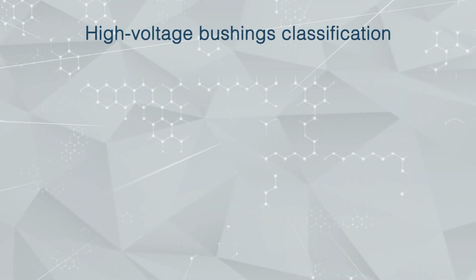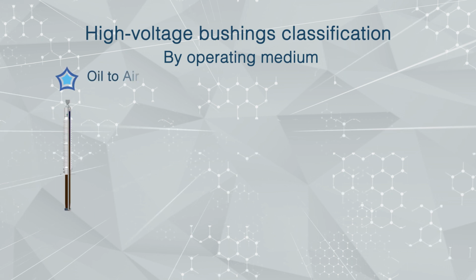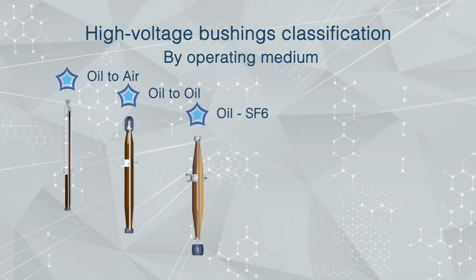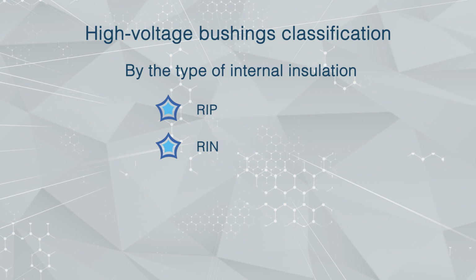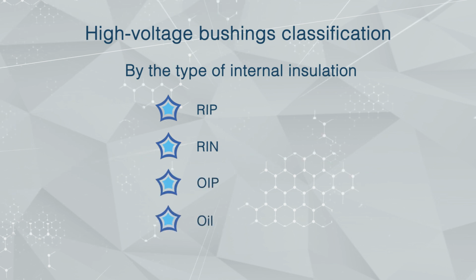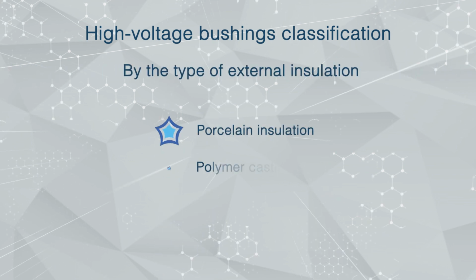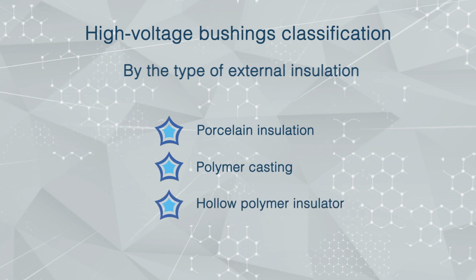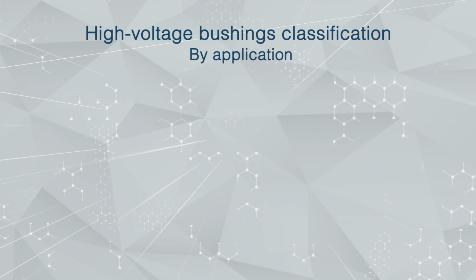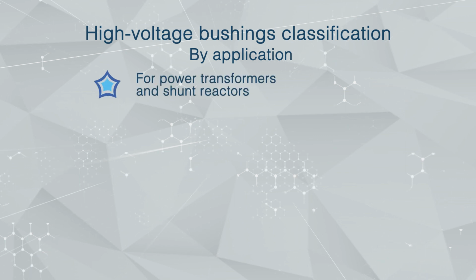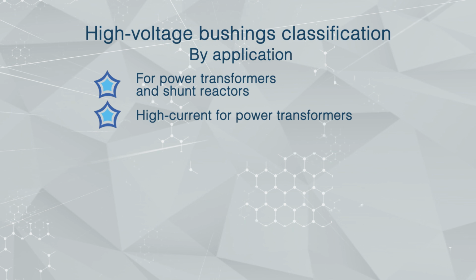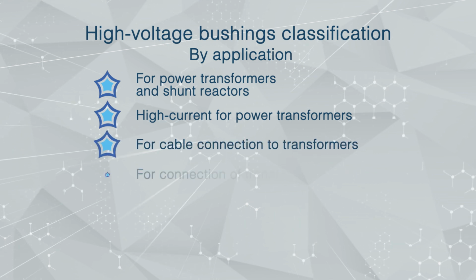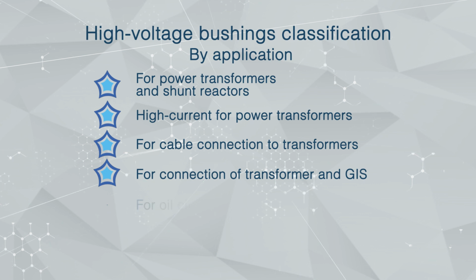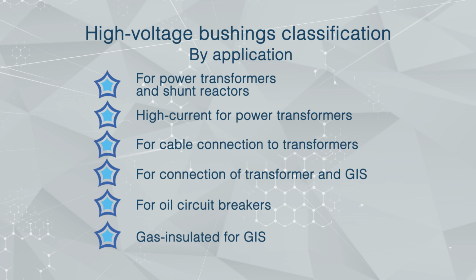High-voltage bushings classification. By operating medium: oil to air, oil to oil, oil to SF6, SF6 to air, air to air. By the type of internal insulation: RIP, RIN, OIP, oil, SF6. By the type of external insulation: porcelain insulation, polymer casting, hollow polymer insulator. By application: for power transformers and shunt reactors, high current for power transformers, for cable connection to transformers, for connection of transformer and GIS, for oil circuit breakers, gas insulated for GIS.